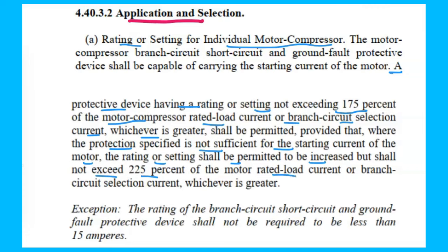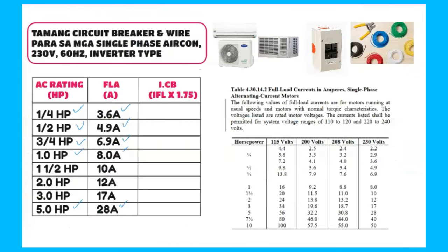So, ang ibig sabihin nito, to size up the circuit breaker, dapat shall not exceed sa 175%. Or hindi rin siya mag-exceed sa 225%. But meron siyang exception. So for the rating of branch circuit, short circuit and ground fault protective device shall not be required to be less than 15 amperes. So dapat ang circuit breaker mo daw or yung ground fault protective device hindi siya bababa ng 15 amperes. Okay? And then based doon sa code kanina, ang sabi is shall not exceed 175%.